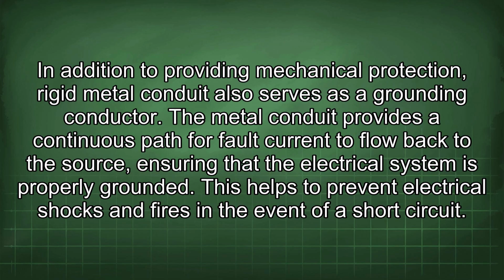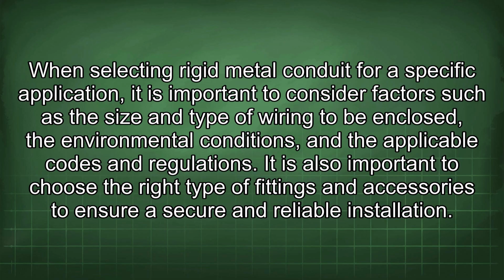In addition to providing mechanical protection, rigid metal conduit also serves as a grounding conductor. The metal conduit provides a continuous path for fault current to flow back to the source, ensuring that the electrical system is properly grounded. This helps to prevent electrical shocks and fires in the event of a short circuit. When selecting rigid metal conduit for a specific application, it is important to consider factors such as the size and type of wiring to be enclosed, the environmental conditions, and the applicable codes and regulations.